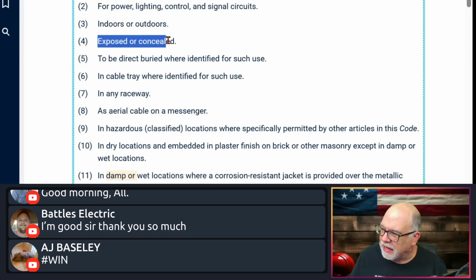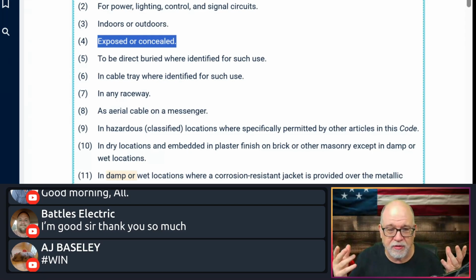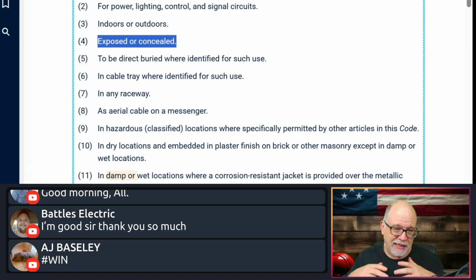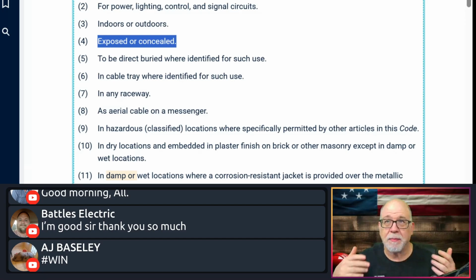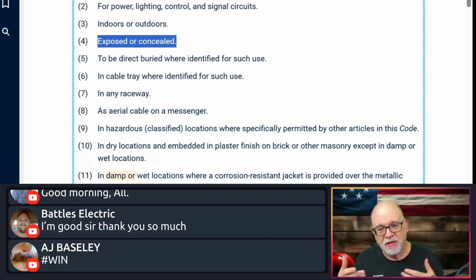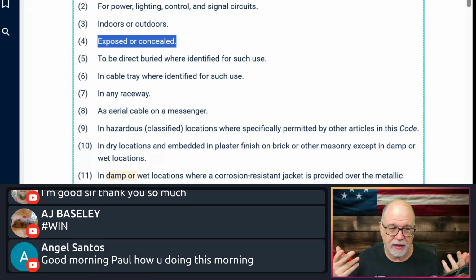Exposed or concealed, I can use MC cable in the wall. I can use MC cable exposed on the wall, but again, not where we're subject to physical damage, but I can use it on the wall. I can use it above a suspended ceiling. I can even use it in an environmental airspace that's acting like a plenum. I can use it in there without any additional ratings. Okay, it doesn't have to be plenum rated to use MC in environmental airspace. Okay, that type of thing.